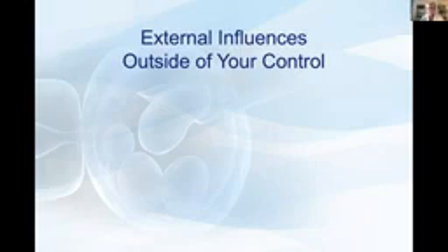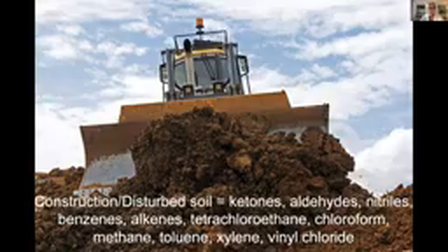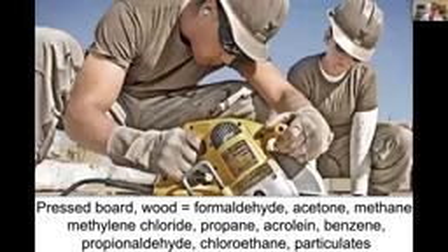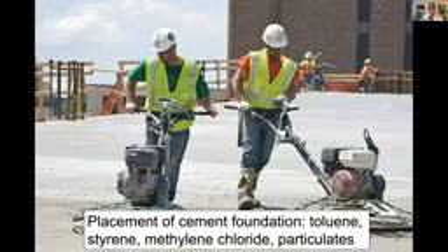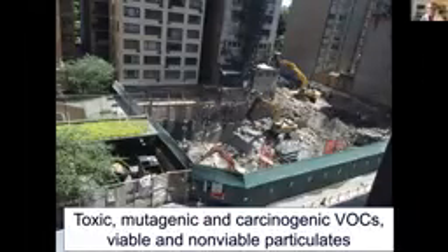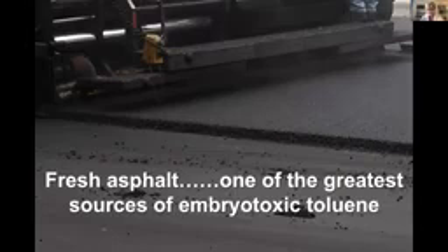So beginning with external sources, as hard as we tried, we could not control the activities of our neighbors. Common activities such as construction, moving soil, construction cutting through board and wood, finishing a cement foundation, demolition, asphalt, fresh asphalt. This probably impacted us in 4 different cycles, and where they resurfaced a medevac pad on the opposite side of the hospital campus where our laboratory was, we had parts per billion of toluene, which is highly embryotoxic, enter our laboratory, and that was one of the causes of compromised cellular and clinical outcomes.